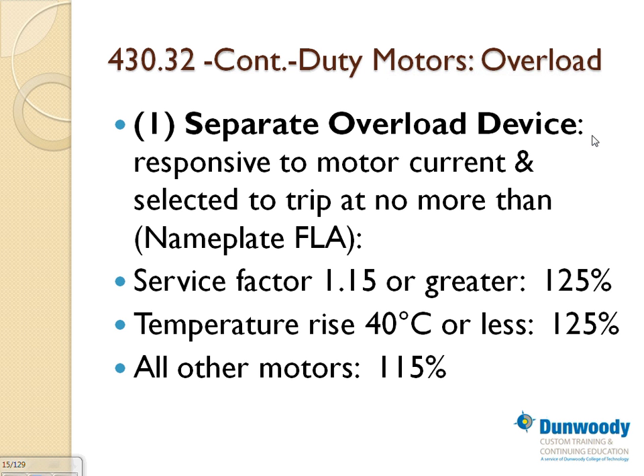Meaning, if you have a 100 amp motor, you put 15% extra on that motor to overload, because you have to allow the motor to overload momentarily, right? Or for a while. Otherwise, every time there's a little bit of load, it's going to trip. It becomes awful. So that's how you size your overload, and all based on a very important concept: nameplate full load amp. Nameplate full load amp. Any comments, guys, about overload? Overload.